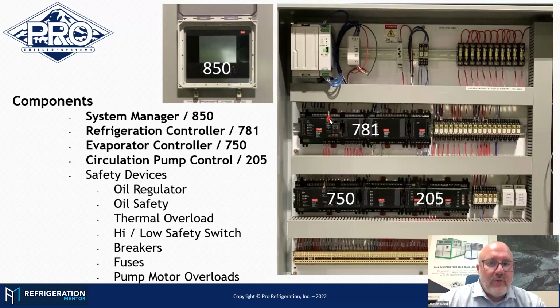Well, there was one loose wire on the 781, and it was giving intermittent communication alarm emails that we were receiving. We were able to identify that with the technician in the field. Like, we probably just have a loose wire. It's not the controller that's bad.